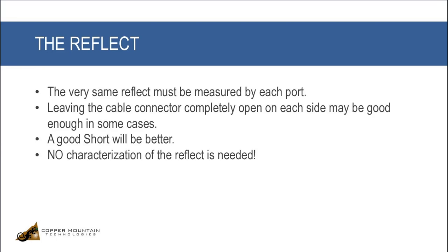As I said, the very same reflect must be used for each port. So if we use just open connectors, well, let's make sure they're kind of centered like this and they're not pushed over to the side, and we'll call this a reflect and this a reflect. It would be better to use a short. No characterization of the reflect is needed.